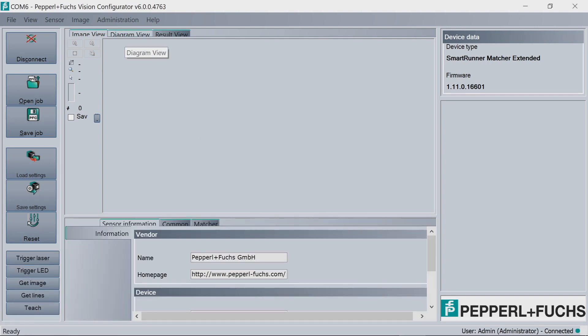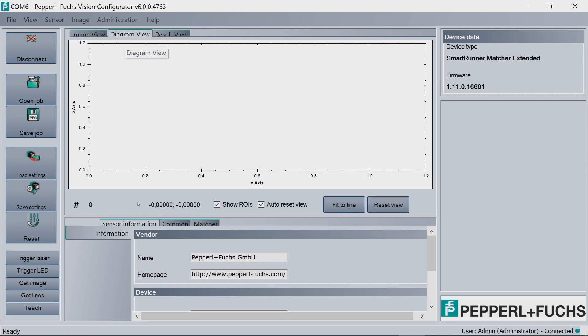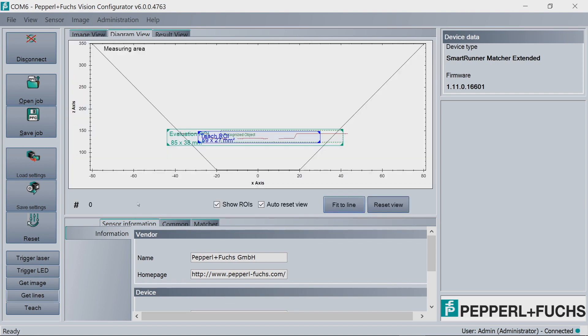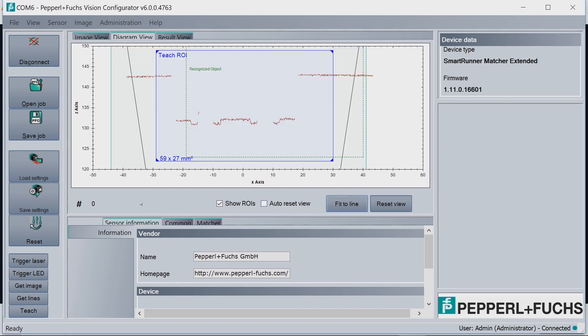This is the initial screen. The first thing we want to do is go to Diagram View. So again, with the target in place, we want to hit Get Lines. And what this shows us is exactly what the SmartRunner is scanning. So then we want to turn off Auto Reset View and hit Fit to Line. This kind of zooms in on the target. Now if you look at the Diagram View, you can see the line profile that we have for the rivet.